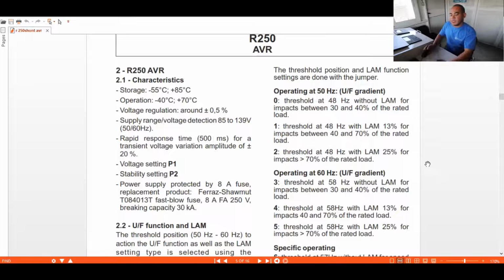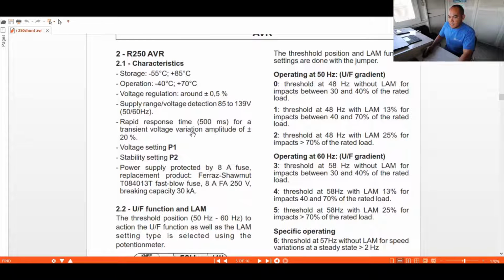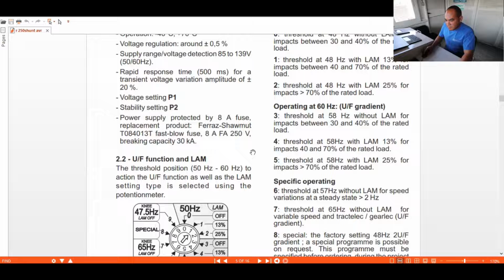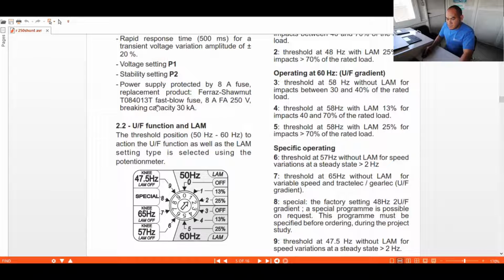So let's go for the characteristics of our AVR. It can operate from minus 40 degrees to 70 degrees Celsius. The voltage regulation is around plus minus 0.5%. The supply range, voltage detection, is 85 to 139 volts, 50-60 hertz, and the rapid response time is 500 milliseconds for a transient voltage variation amplitude of plus minus 20%. We just talk about the important ones. Your power supply protection is an 8 ampere fuse, and the breaking point is 30 kiloamps.